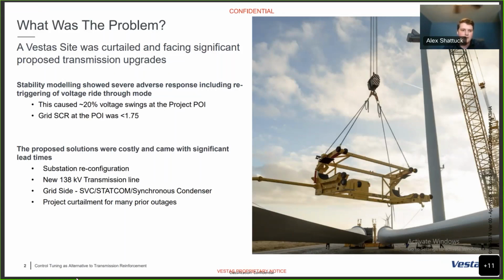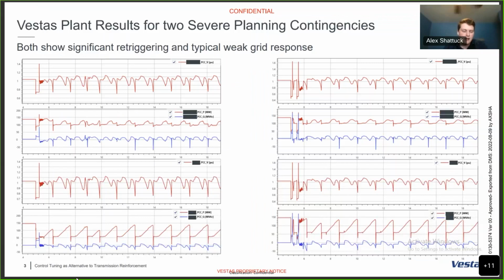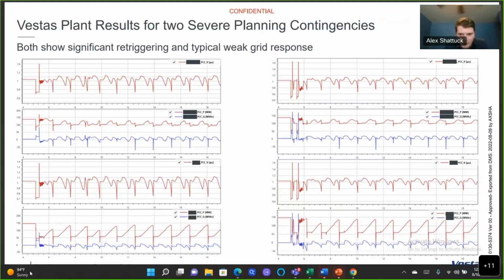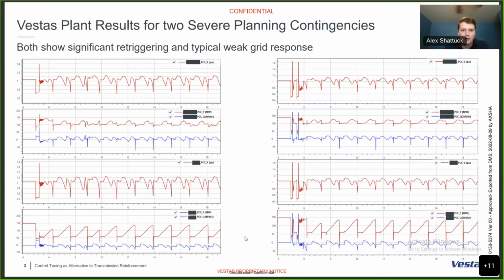So, next slide please. These are the plots we got, from PSSE. We started this study in PSSE because that's what the ISO's consultant running the studies was using. What we see here is what they were closing out talking about - you can see the top plots for both of these, it's 20% voltage just swinging over and over again, and you'll see the reactive power and the power also just ramping up and down.